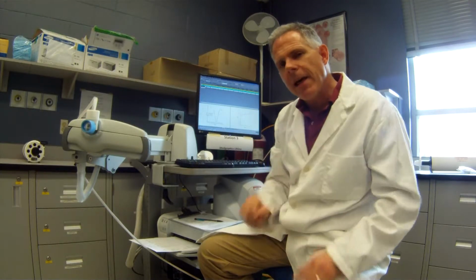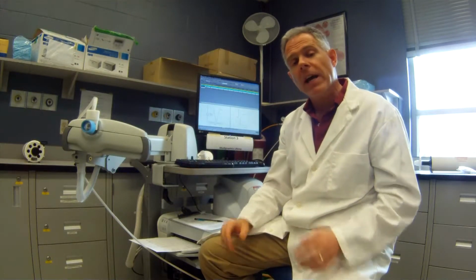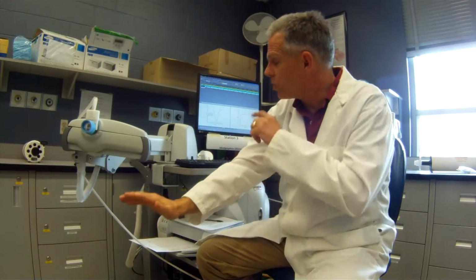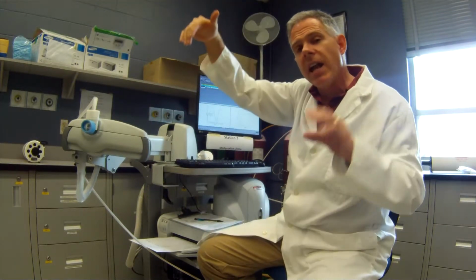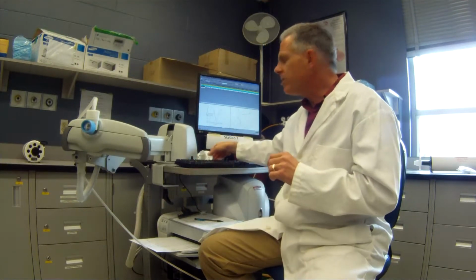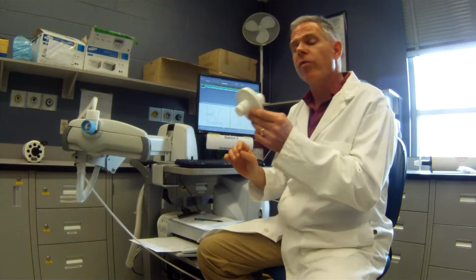Now, when they take that big breath in, they're going to notice a change. They're going to be breathing in 100% oxygen. Okay, so it's important to let them know that. So we start off with nice, even breathing, and then when we feel they're ready, we trigger the machine so they take a big breath in of 100% oxygen, all the way in as much as they can. And here's the trick: it's got to be at a nice, even flow rate. There are some guides on the machine, and it's a slow flow rate. So you want to demonstrate to your patient that they're going to take a big breath in and blow it out, but at relatively low, slow flow rates.